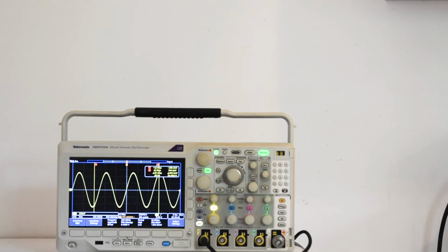In the bottom line, left edge of the display, measurement readouts show the selected measurements. You can select up to 4 measurements to display simultaneously. A triangle symbol appears instead of the expected measurement if a clipping condition exists. Part of the waveform is above or below the display. To obtain a proper measurement, turn the vertical scale and position knobs to make all of the waveform appear in the display.